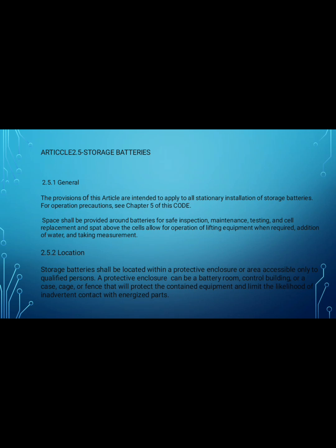2.5.2 Location. Storage batteries shall be located within a protective enclosure or area accessible only to qualified persons. A protective enclosure can be a battery room, control building, or a case or fence that will protect the contained equipment and limit the likelihood of an inadvertent contact with energized parts.